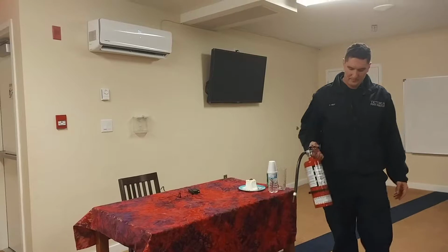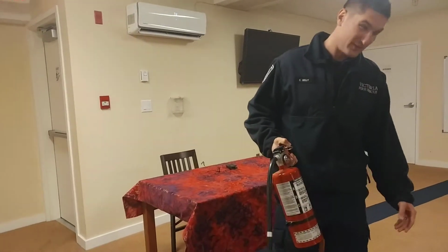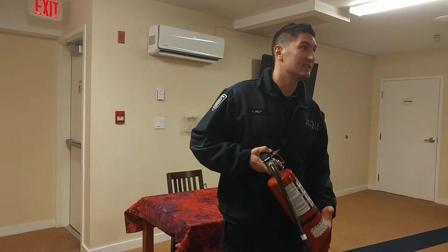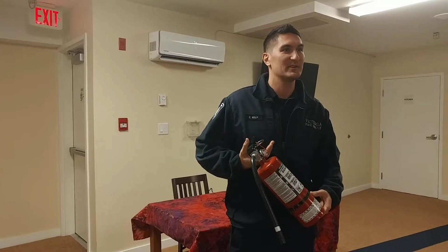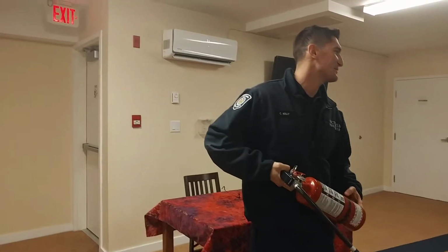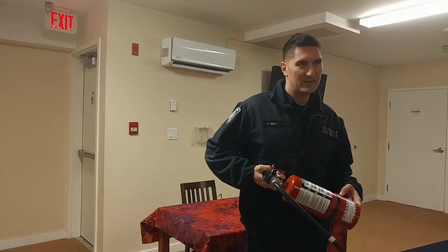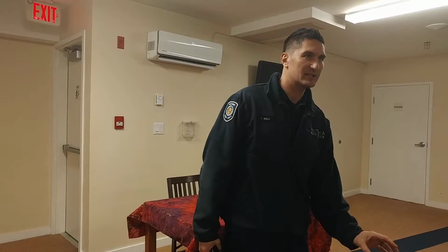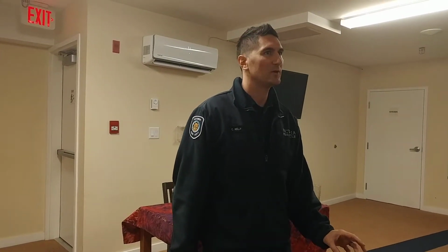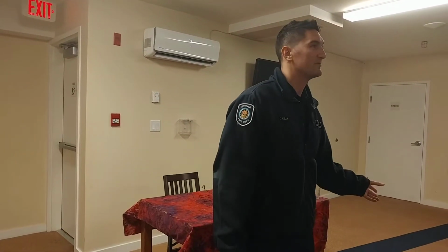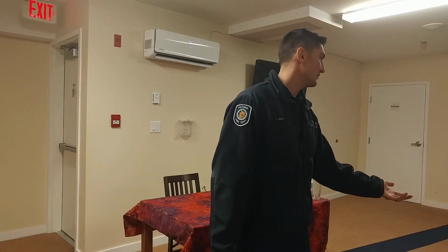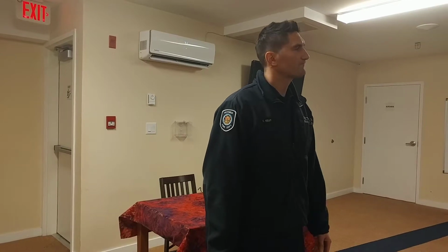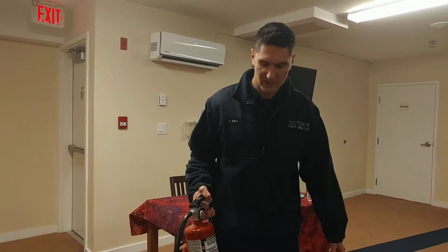So typically you'll get 20, 30 seconds out of these. It's not very long. I'm probably being very generous on that. Maybe 15 seconds is a little more accurate. It's because they're meant for small growth fires. So like something really in its early stages of fire growth, just started. Something in a trash can, a small chair like this would be fine. A little pot on the stove type of fire. Those would all be great with an extinguisher like this.